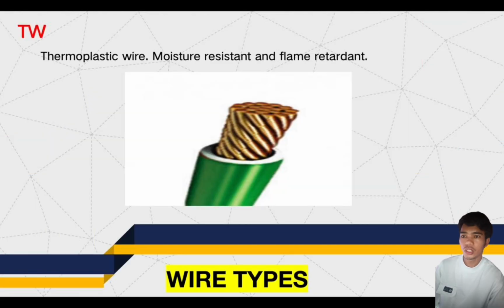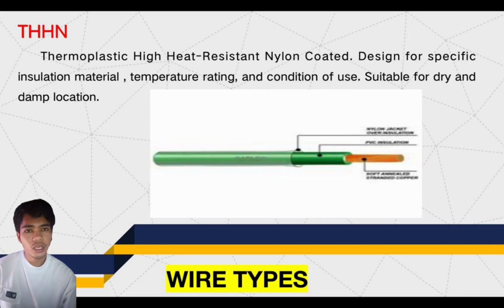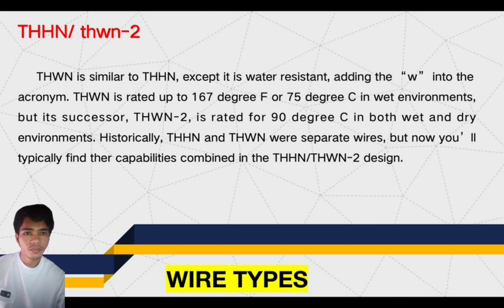Wire sizing. TW: thermoplastic wire, moisture resistant and flame retardant. THHN: thermoplastic high heat resistant nylon-coated, designed for specific insulation material, temperature rating and condition of use, suitable for dry and damp locations. THHN, THWN-2. THWN is similar to THHN except it is water resistant, adding the W to the acronym. THWN is rated up to 167 degrees F or 75 degrees C in wet environments, but its successor THWN-2 is rated for 90 degrees C in both wet and dry environments.